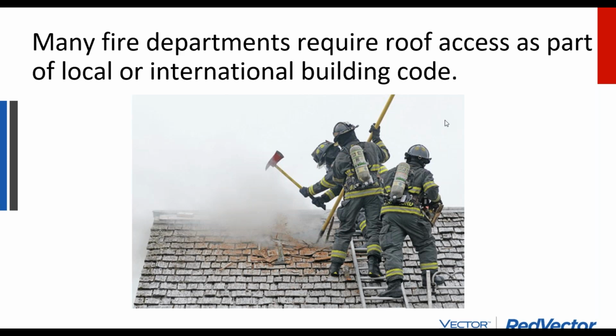Well, if your solar array is covering the rooftop, then the firemen can't cut a hole in the roof. And then there's the additional hazard of, that solar array is on, and by nature it's always on. If the sun's up, the solar panel's on. So the firemen get concerned about electricity from the solar array arcing into the building.